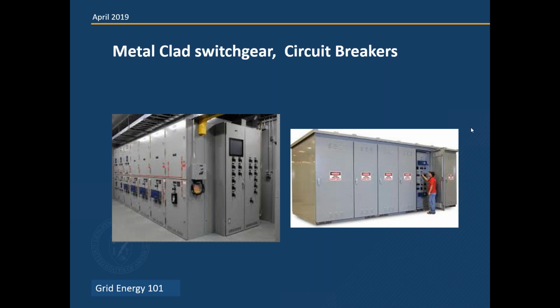And so if you throw out a bunch of 50 megawatt gas turbines out there, they don't have any spinning mass behind them. And when those problems happen on the electrical system, and trust me, they're happening every day, we need the strength of the interconnected system and our large generating units, especially hydro, so we can ride through those frequency deviations. And if you start creating all these storage units, and yes, you may be off peak where you're discharging those storage units, what happens when there's a fault on the system? I'm sure there's an electrical engineer or two around the world who could say, Pete, I don't know what you're talking about, or you're crazy. And that's okay. But from a real practical system operator, one of the guys that's been responsible for operating the electrical system since 1986, that's something that we need to keep in our back pocket and be aware of.